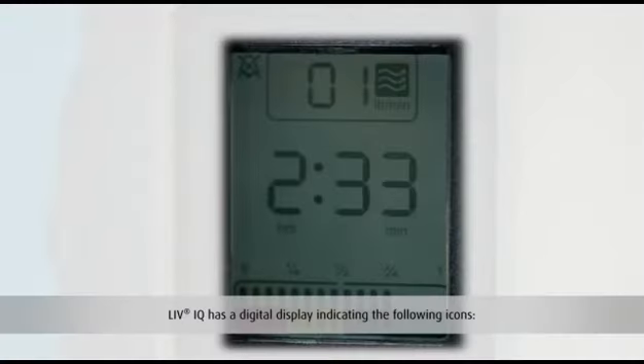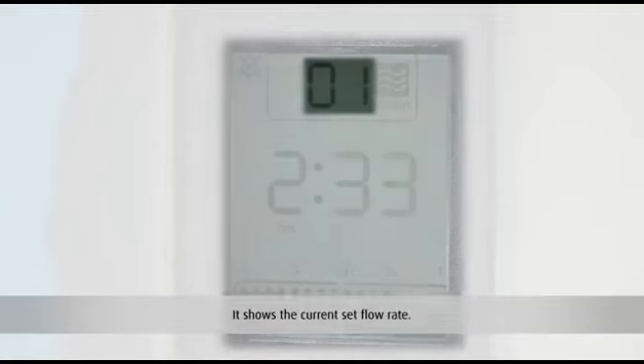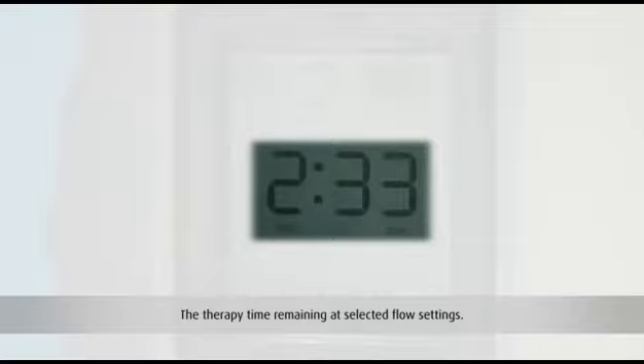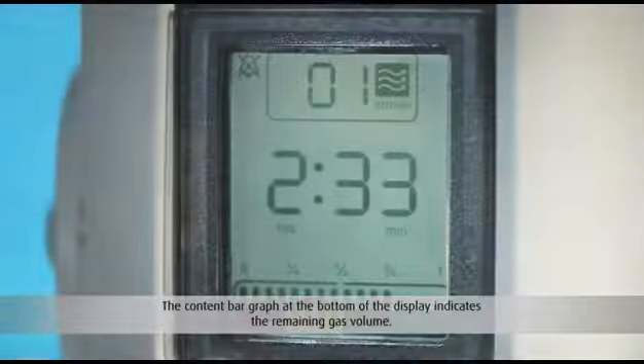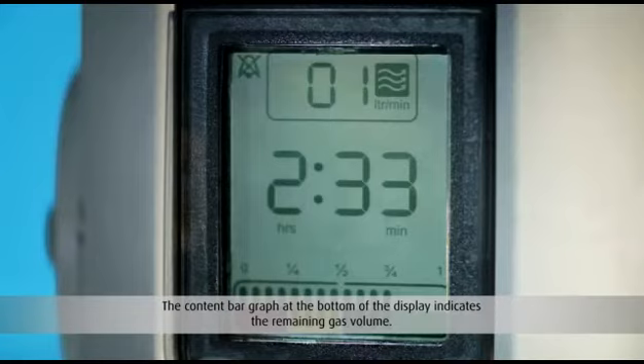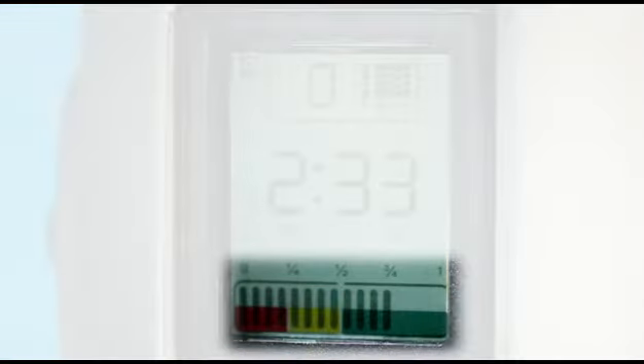LIV IQ has a digital display indicating the following icons. It shows the current set flow rate. The flow symbol indicates that the flow is active. The therapy time remaining at selected flow settings. The content bar graph at the bottom of the display indicates the remaining gas volume. The diamond icon indicates that you are using a new and full cylinder.